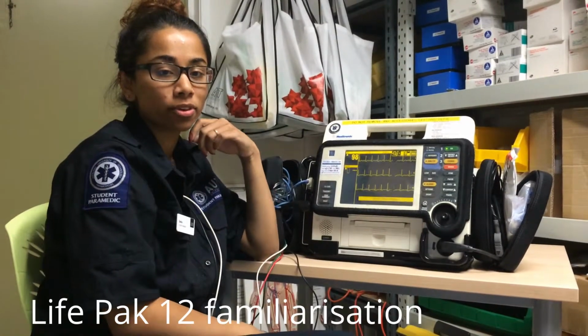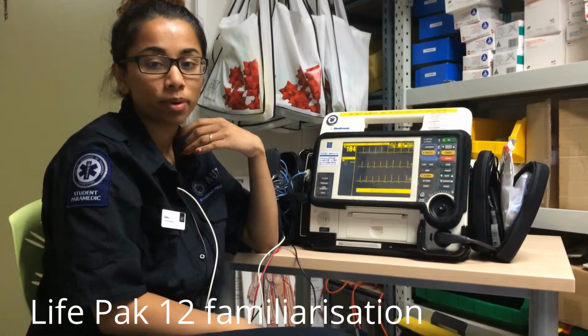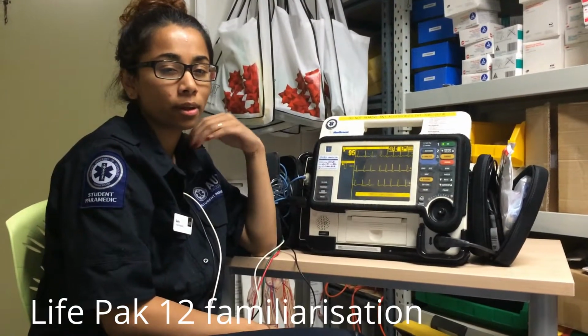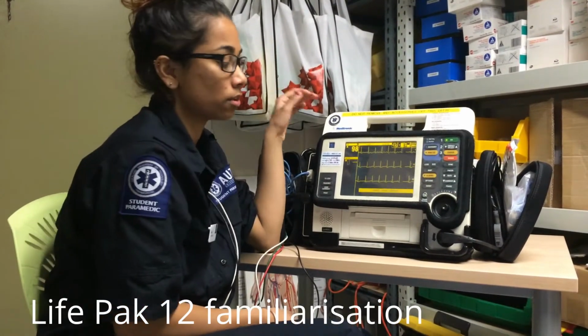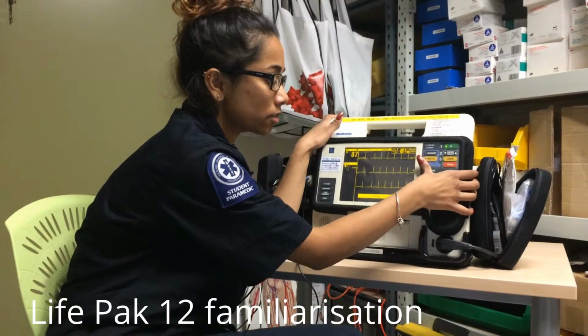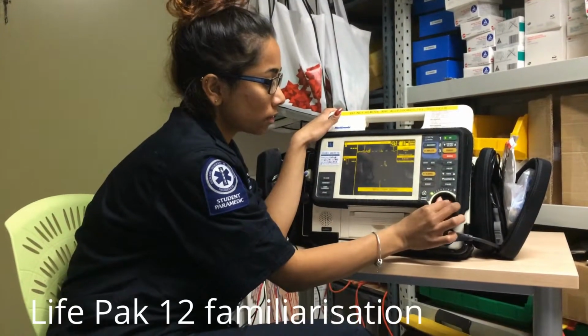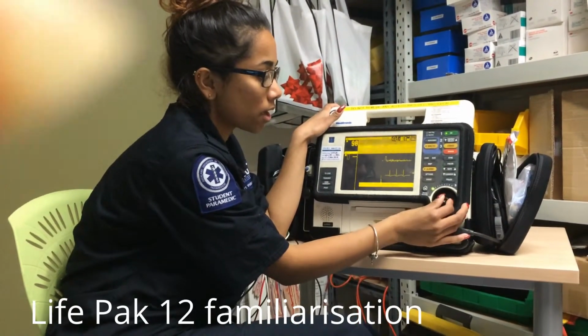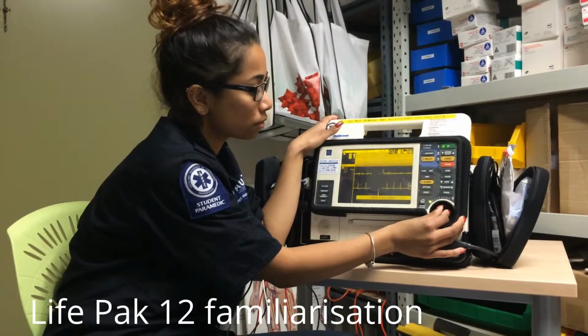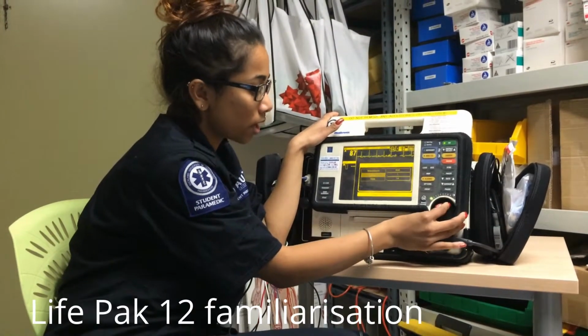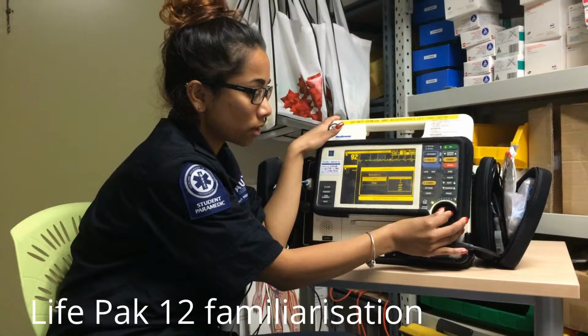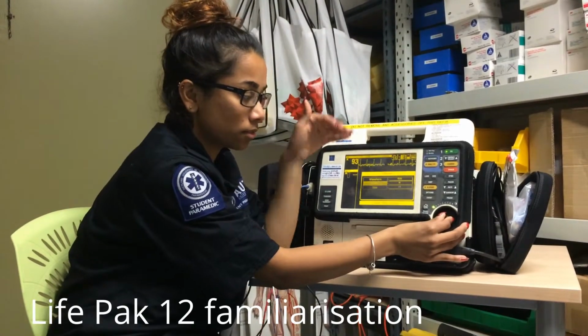We're changing from manual mode to AED mode. You can choose between the leads by pressing the lead button. It gives you a number of options, and you can simply choose whichever one you want, and it will come up on the live feed. So you click lead, the one you desire, and you can also then select through the channels like so.